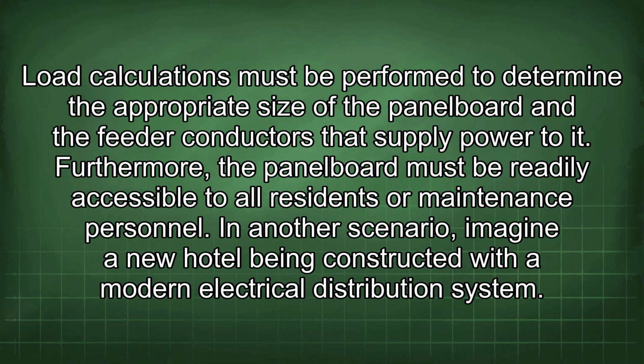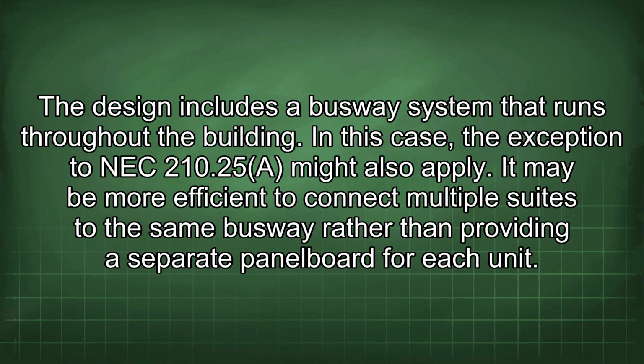In another scenario, imagine a new hotel being constructed with a modern electrical distribution system. The design includes a busway system that runs throughout the building. In this case, the exception to NEC 210.25 might also apply. It may be more efficient to connect multiple suites to the same busway rather than providing a separate panel board for each unit.